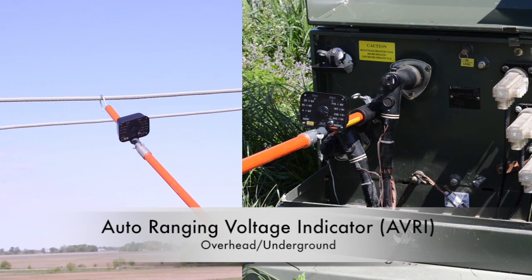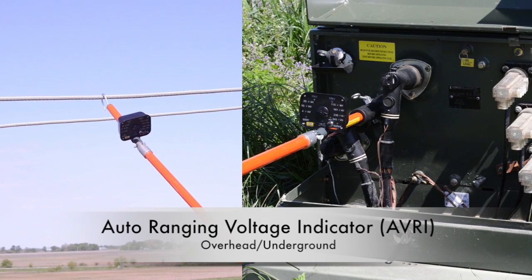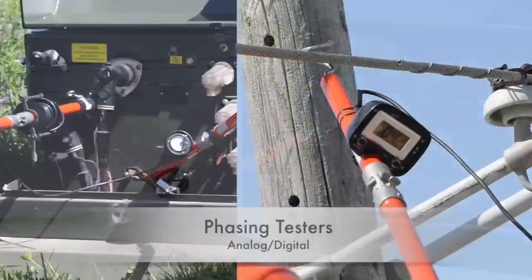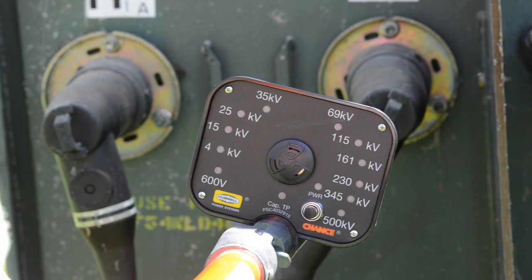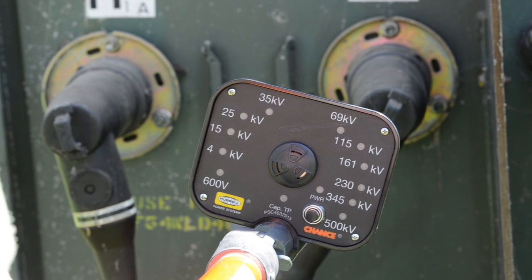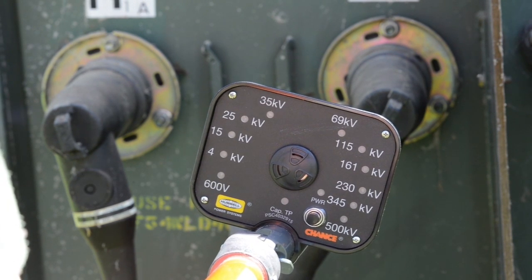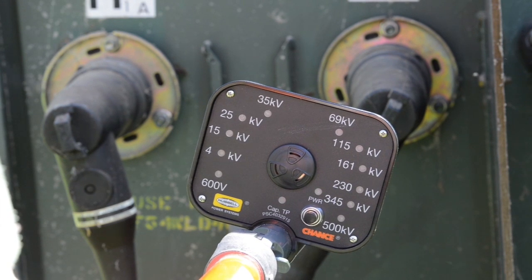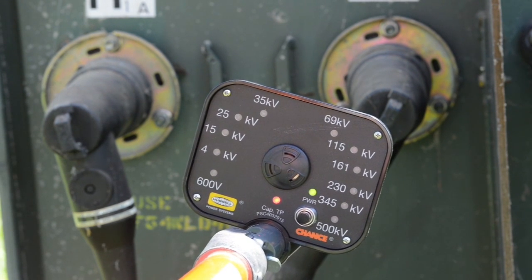In this video, you'll see typical overhead and underground applications of the Chance Auto Ranging Voltage Indicator and phasing testers, both analog and digital. Beginning with the Full Range Auto Ranging Voltage Indicator, referred to as the AVRI for short, start by pre-checking it for operable condition using the Voltage Indicator Tester specified in the RV instruction manual.